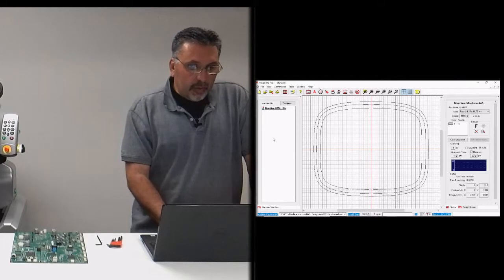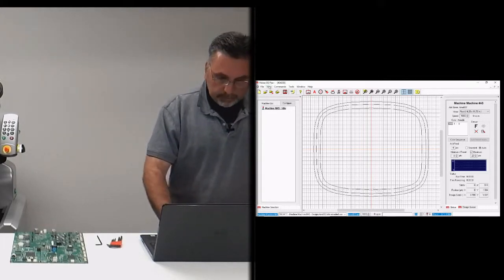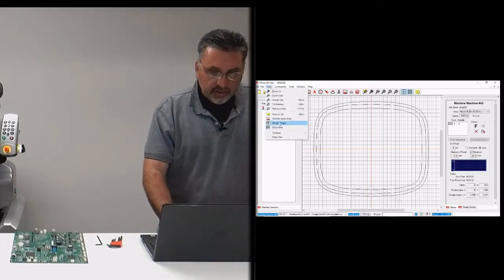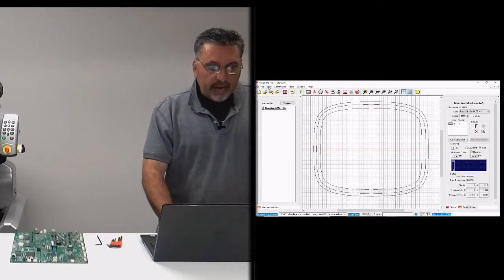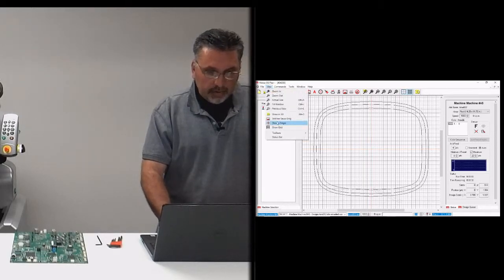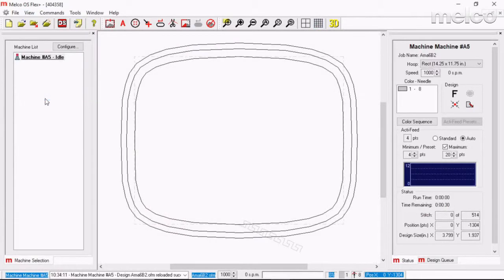So now that we have set the serial number and the name of the machine, when it comes back, it's going to give us that error again. Okay. That's going to stay. Stored color change calibration values do not match. Now's where we're going to correct that error.